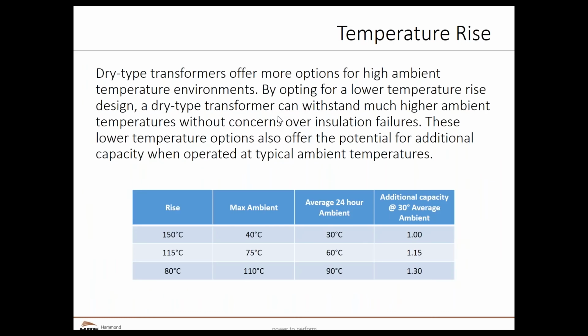So again, we've had some other graphs here in the temperature rise options. You can see here that depending on the temperature rise, an 80°C temperature rise transformer, which is a common option in dry type, can actually handle an ambient temperature hotter than the boiling point of water. You don't have those options with a liquid-filled transformer. So depending on what ambient temperature you're going to run that transformer at, I can either run it at higher ambient temperatures or I can get some additional capacity.